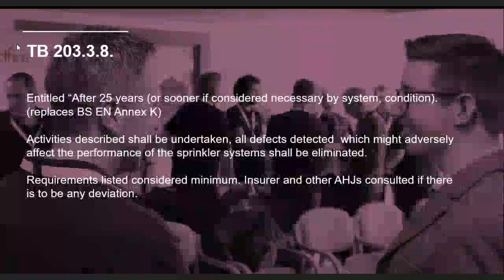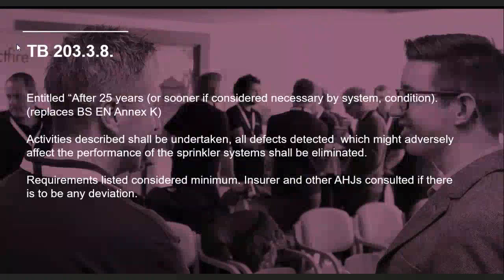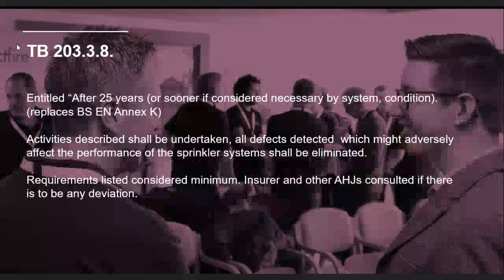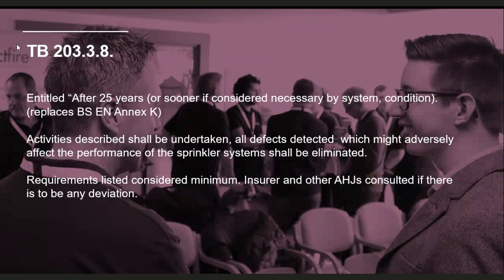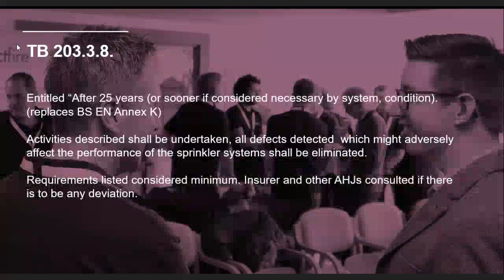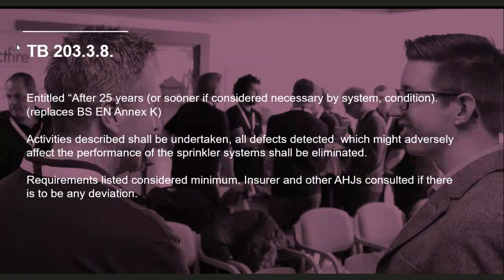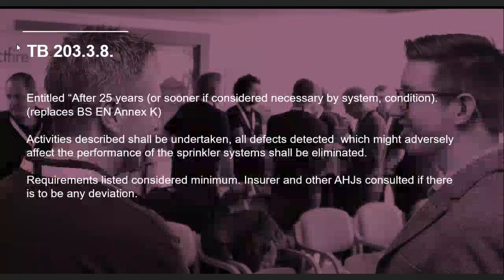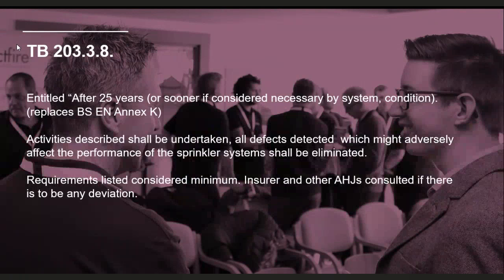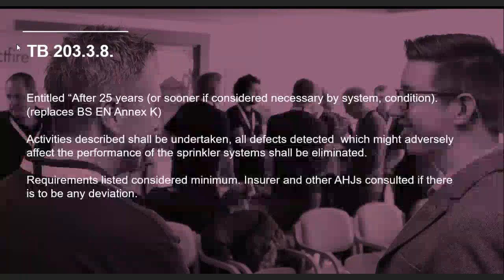So this is what TB203.3.8 says: after 25 years - and this is important - or sooner if considered necessary by system condition, this replaces BSEN Annex K. So the technical bulletin is making clear this overrules what Annex K says, and that 25 years is a maximum time.